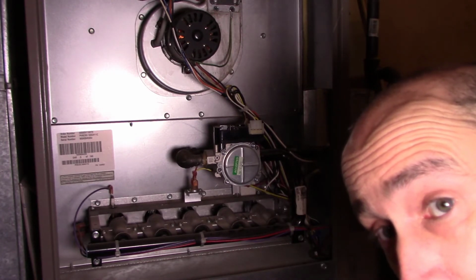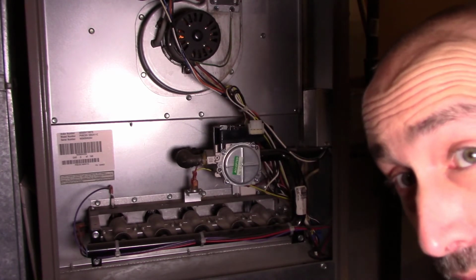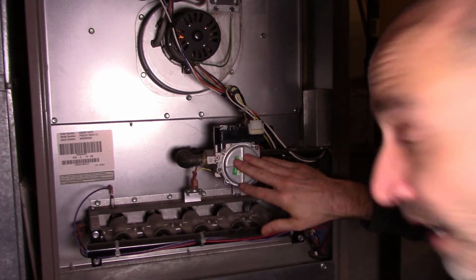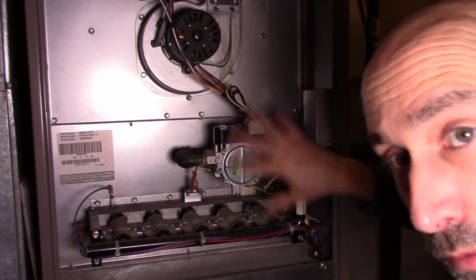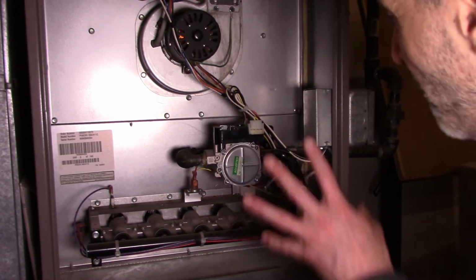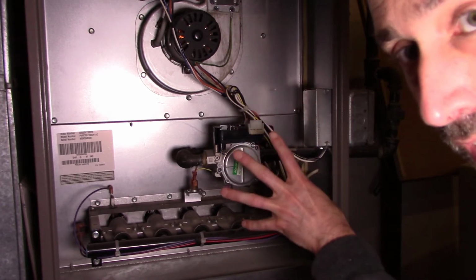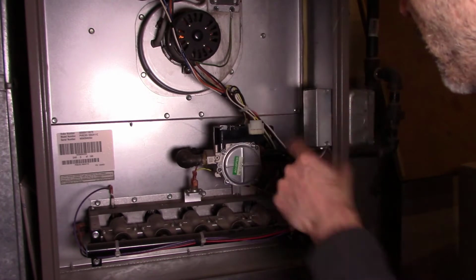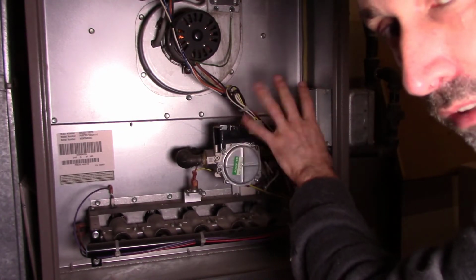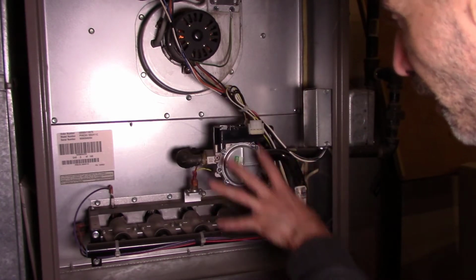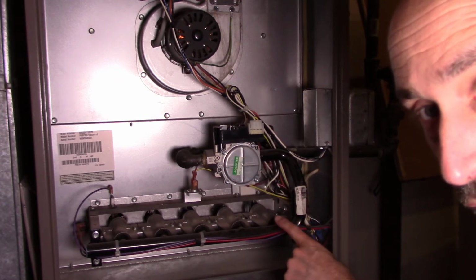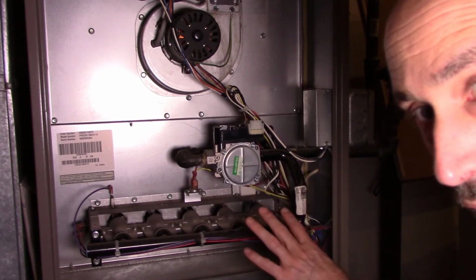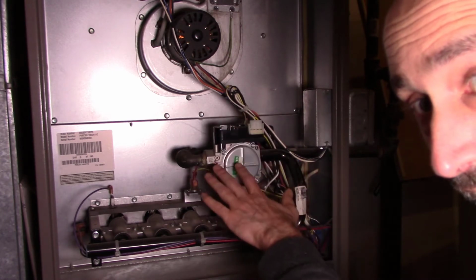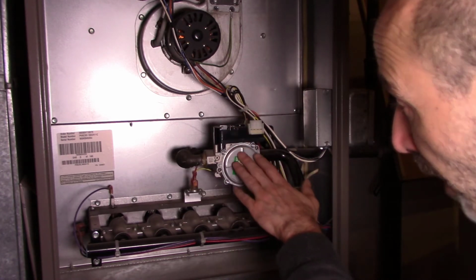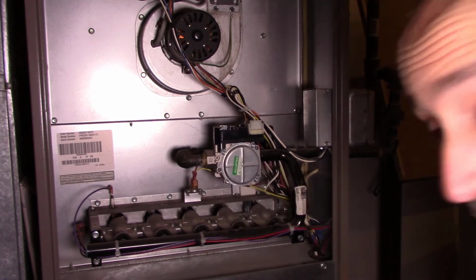Okay, so what happens if that glows, but then nothing happens? You get no flame. Well, that can typically be a gas valve problem. So again, make sure the gas valve is on and no one was monkeying with this. But really, troubleshooting a gas valve is outside of the scope of this. That's a little more in depth than making sure you have voltage to it, which is typically a low voltage, 24 volts. I'm not going to go into that here. But typically if your igniter is clicking or glowing and it doesn't fire, it's a gas valve problem, and you probably should call a professional for that.